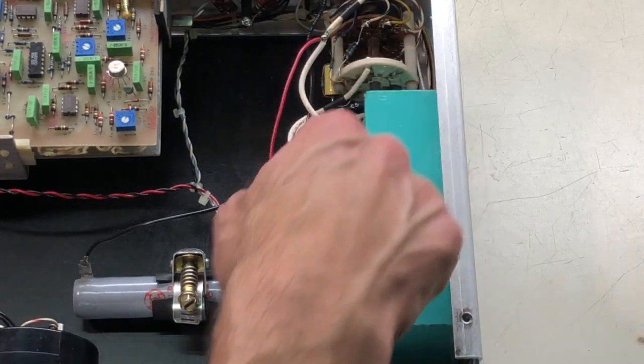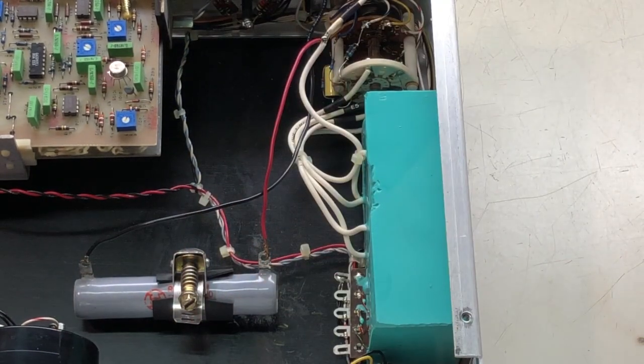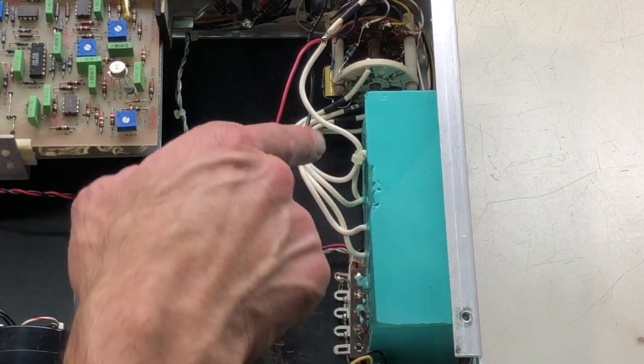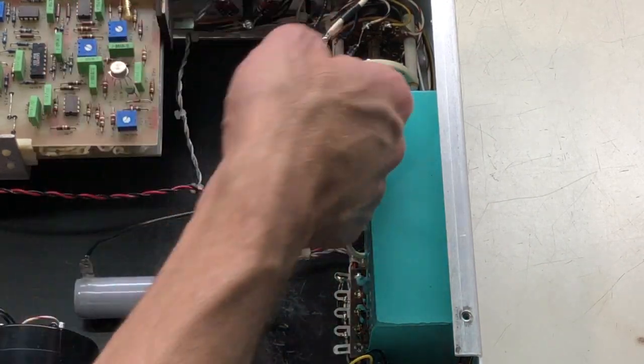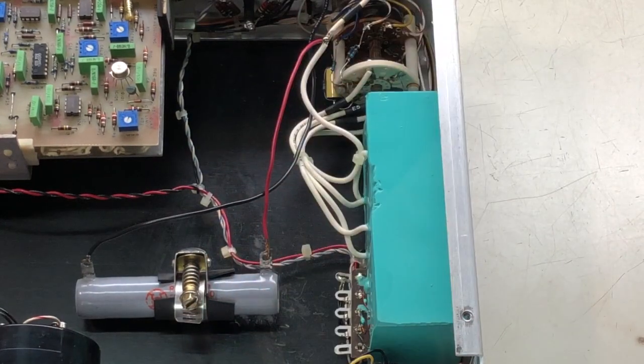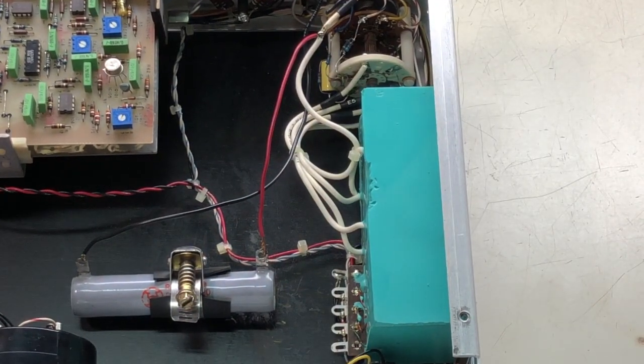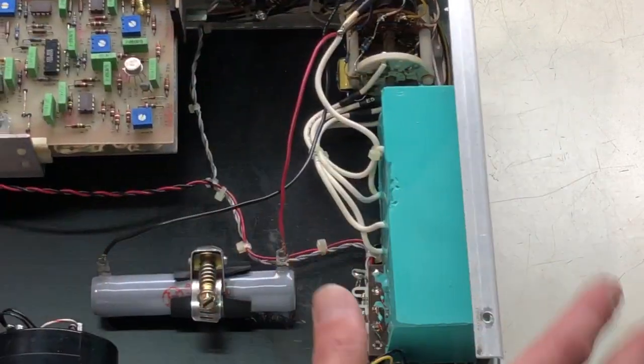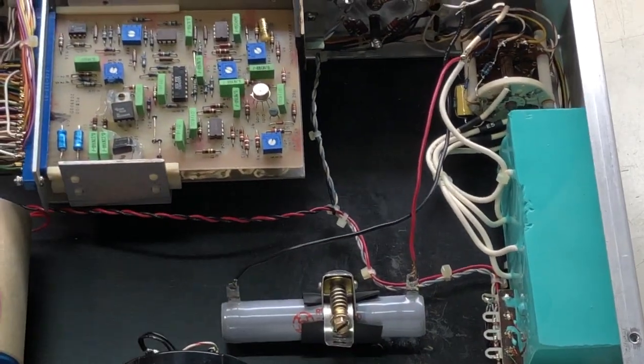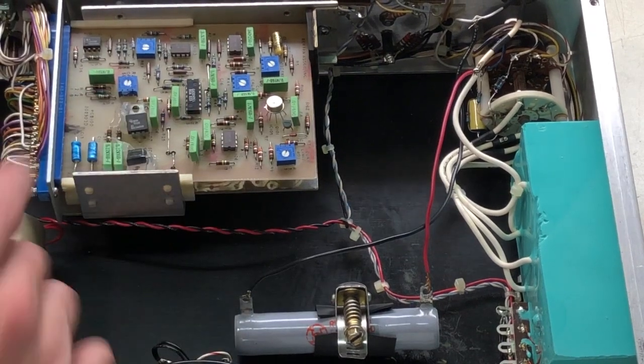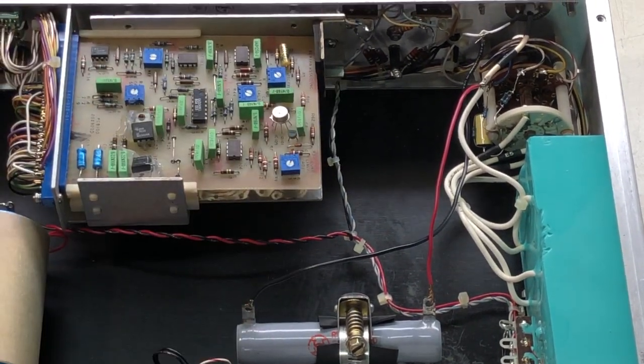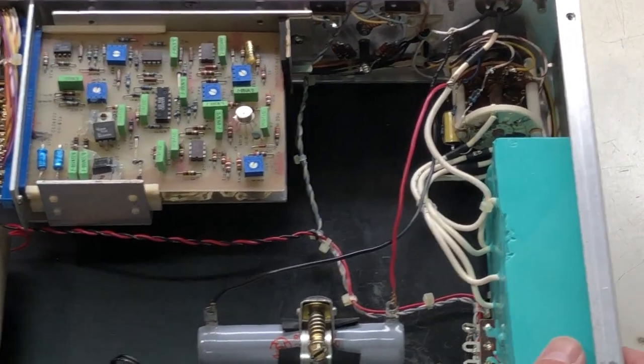In fact, this is the 1,000 volt. If this is set to the maximum, you'd have 1,000 volts on this wire, and the cover is right across here, and they've just left that open. That's not looking too good. So we're going to have to clean that up. Now it looks like everything here is low voltage on the rest of the unit. Of course, these control circuit boards and then probably the driver for the transistors and so on, but all the high voltage is in this module over here.